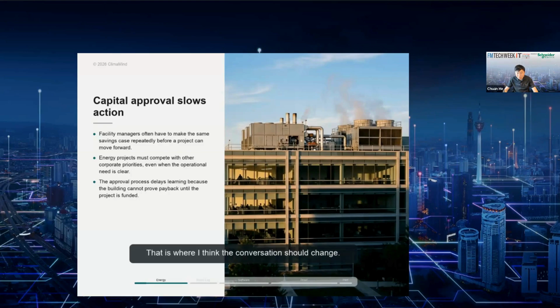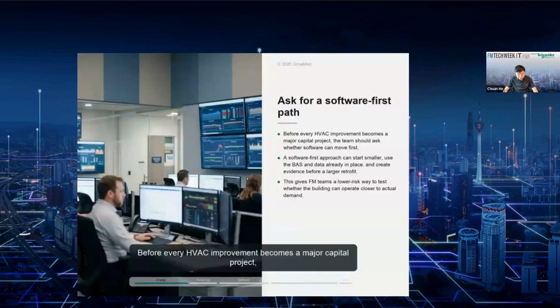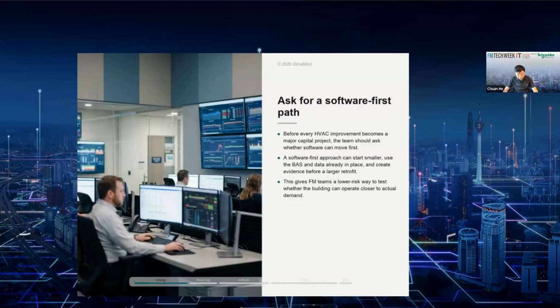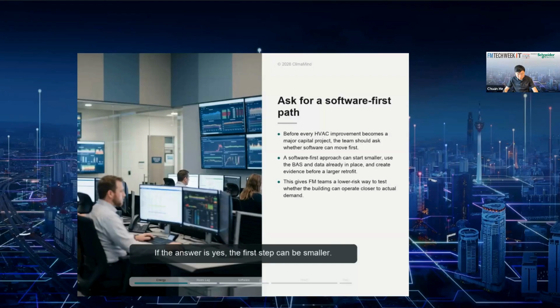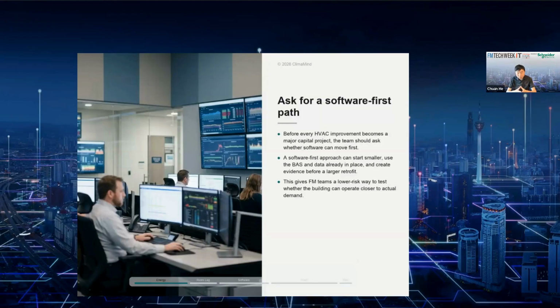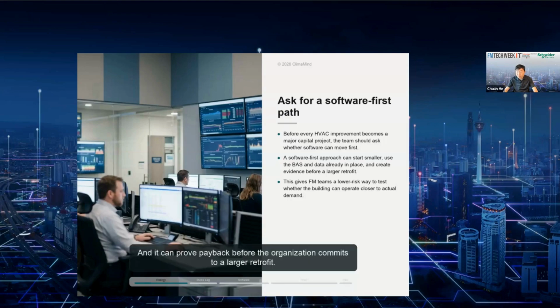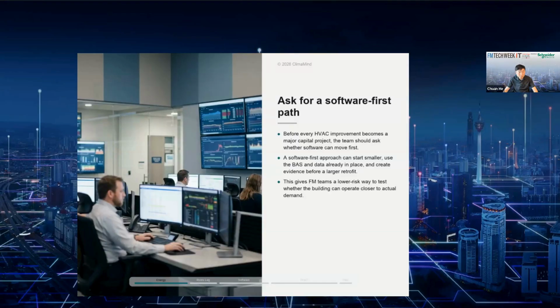That is where I think the conversation should change. Before every HVAC improvement becomes a major capital project, facility teams should ask whether there is a software-first path. Can the building use the BAS it already has, the data it already collects, and the equipment already installed, and operate closer to what it actually needs? If the answer is yes, the first step can be smaller, it can be faster, it can carry less implementation risk, and it can prove payback before the organization commits to a larger retrofit.